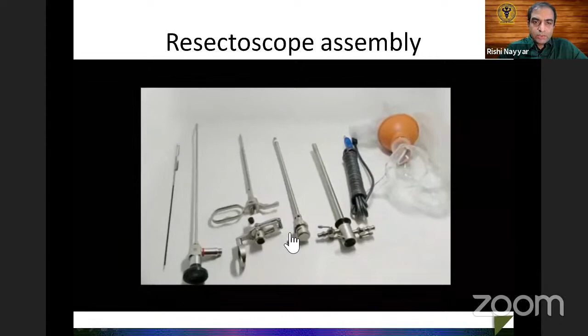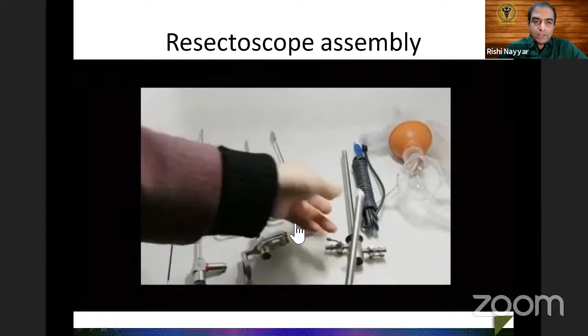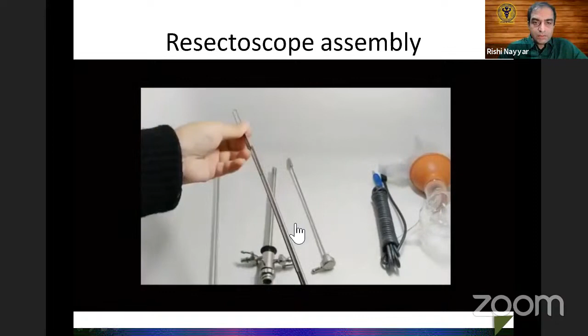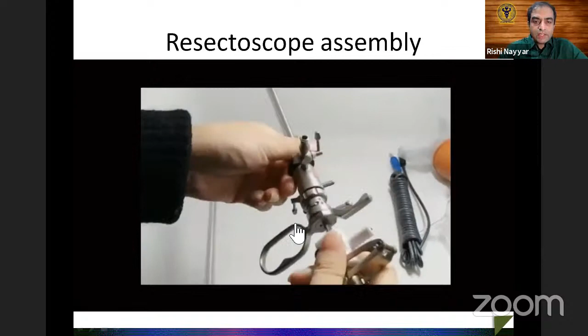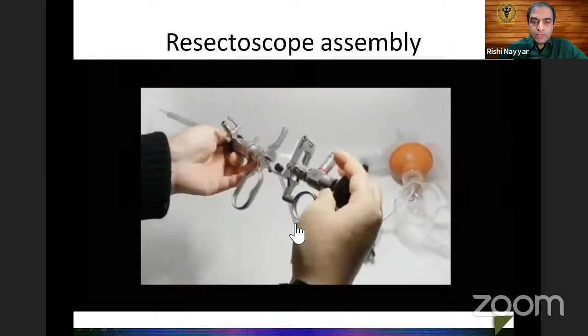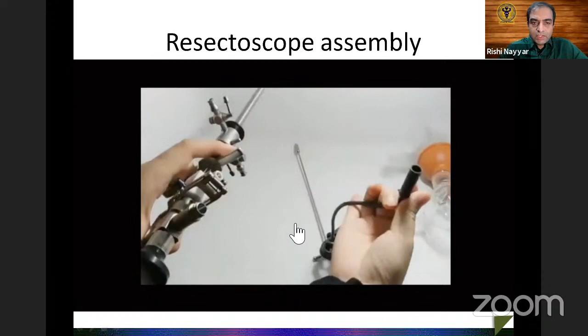So how do we assemble the resectoscope outside? Inside the patient, we obviously put it with the visual obturator inside. So here the inner sheath is being aligned with the outer sheath in a 0 to 0 alignment and then locked. The lock assembly is different with the different manufacturers and has to be learned. So then here again 0 to 0 of the working element is aligned and it is locked in position. After that the telescope is put in position and the electrical cable has to be attached at its proper point wherever it is provided by the manufacturer.